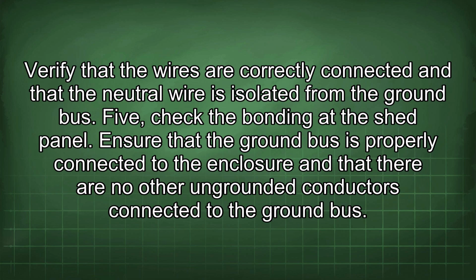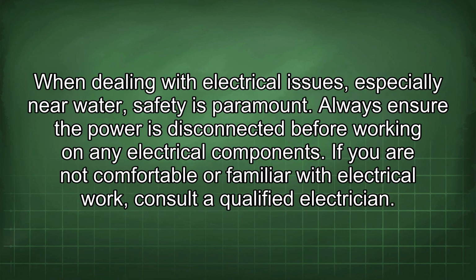5. Check the bonding at the shed panel. Ensure that the ground bus is properly connected to the enclosure and that there are no other ungrounded conductors connected to the ground bus. When dealing with electrical issues, especially near water, safety is paramount. Always ensure the power is disconnected before working on any electrical components. If you are not comfortable or familiar with electrical work, consult a qualified electrician.